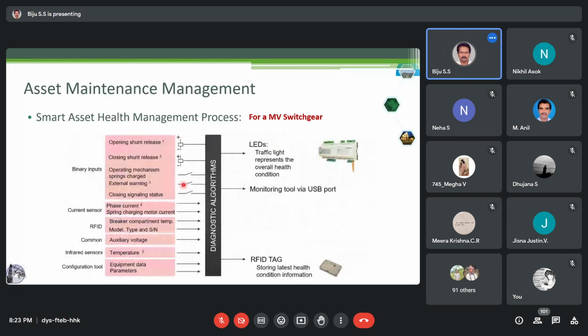Then this is the schematic diagram of how the breaker is being monitored. Binary inputs monitor the operating circuit, the trip coil, the closing coil, the operating mechanism, and the closing or open signal to the breaker. Current sensors will detect the breaker current as well as the spring charging current. RFID will give the breaker information. Then auxiliary voltage will be measured. Infrared sensors will measure the temperature inside the cubicle. Then the configuration will give the equipment data parameters. So all this will be used for diagnostics.